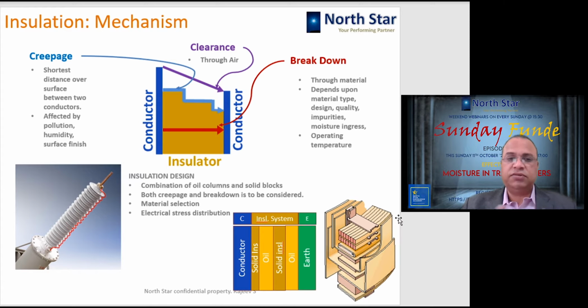So any insulation system design considers all these three factors in building the desired insulation strength. In transformers, it is a combination of oil columns as well as solid blocks, and inside the transformer both creepage and breakdown are considered, and of course the material type which is selected, and how the electrical stress is getting distributed. Here you can see a system which I am showing. This is the live part, this is the earth part, and there are alternate columns of solid insulation and liquid insulation, which is oil in this case. By providing this kind of arrangement, more insulation strength is built into a limited amount of space. This is how the barriers are put in the transformer, so that you have solid insulation supported by liquid insulation on both sides of it.